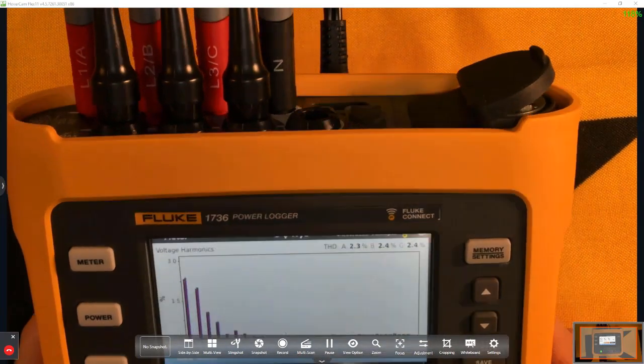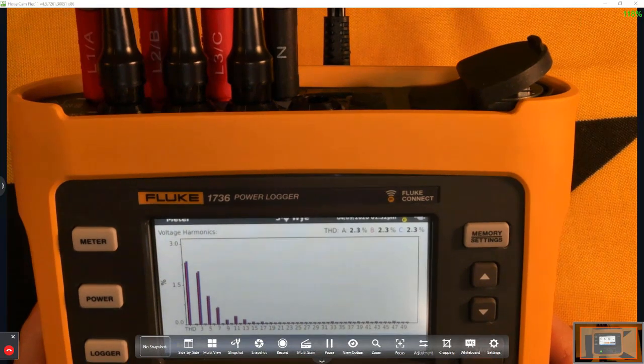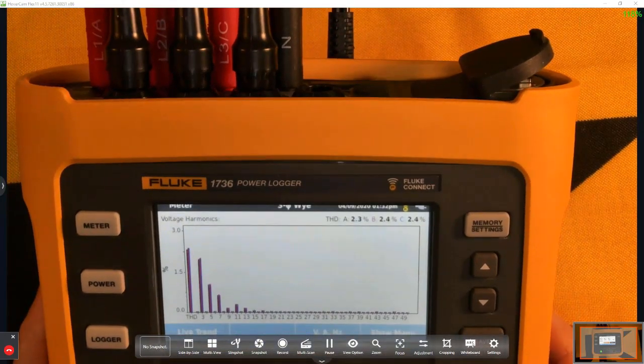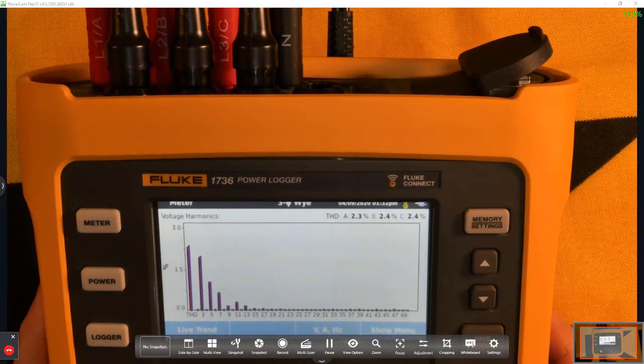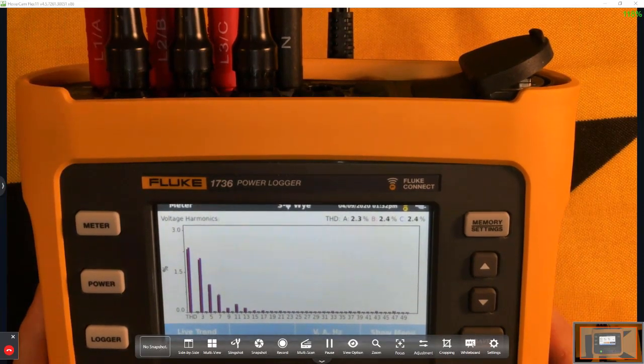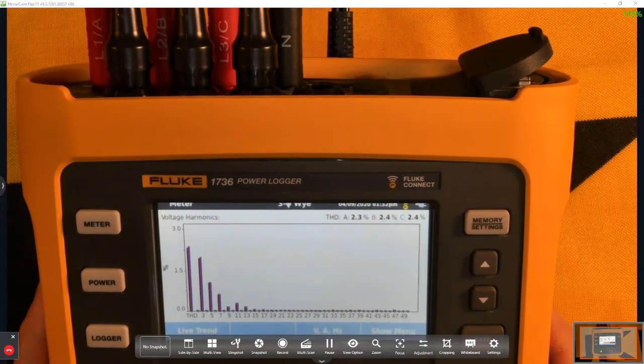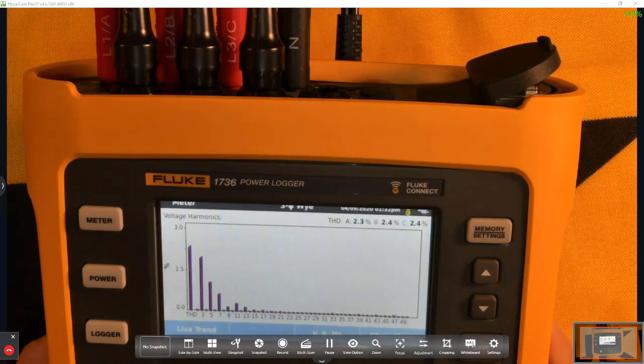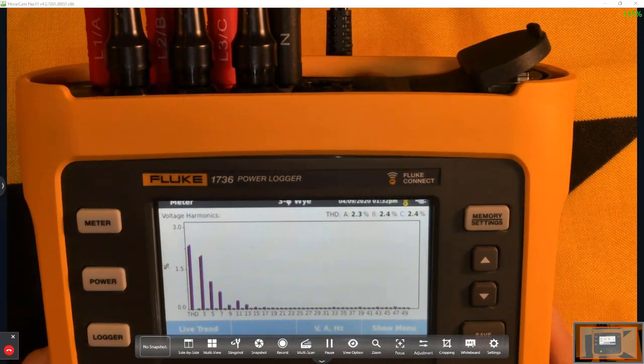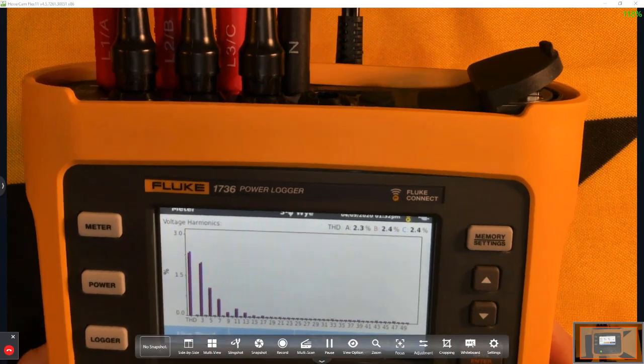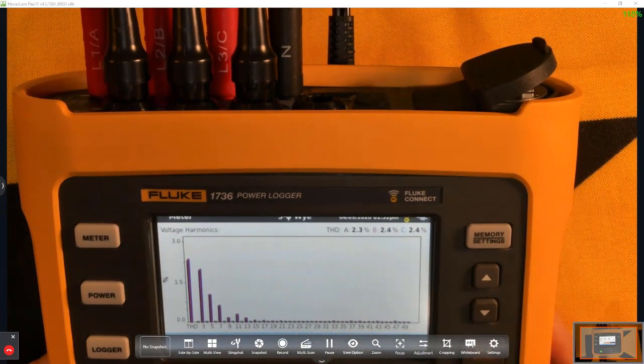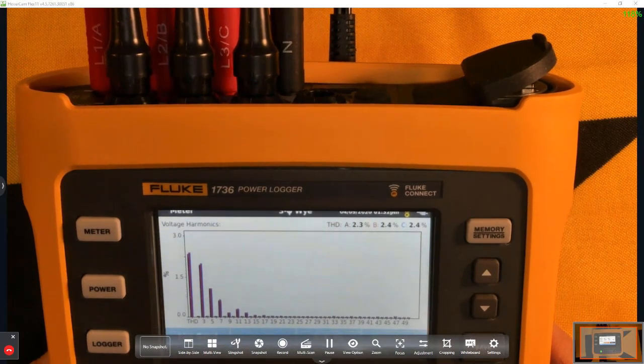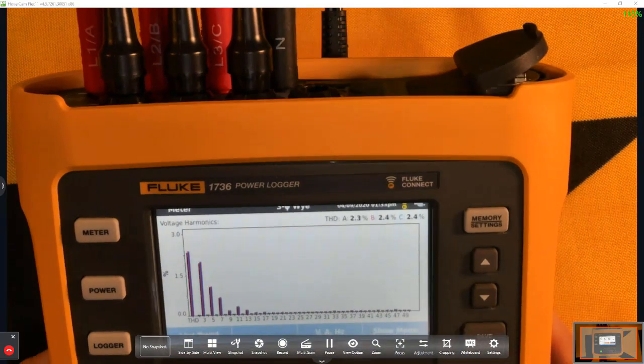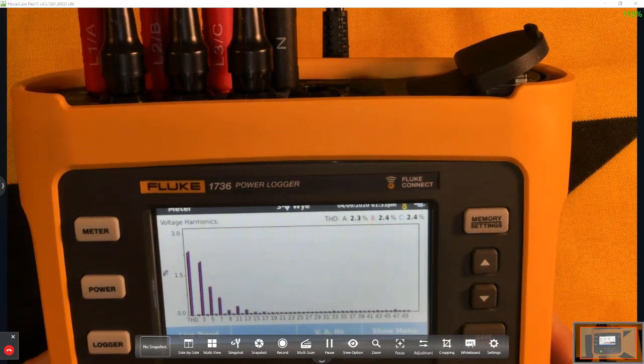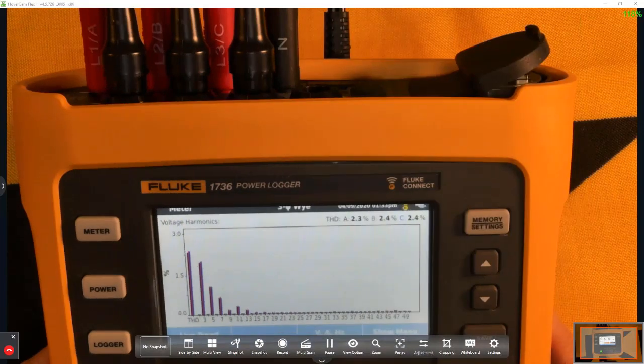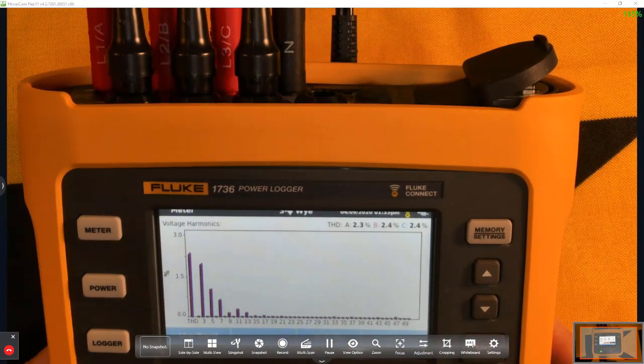The other thing we were discussing is applications involving harmonics. Usually having transformer problems, damaged power factor correction capacitors, or motor loads overheating that maybe weren't before, could be a source of harmonics. The 1736 and 38 give you the ability to measure individual harmonic orders, and if you're using the 32 and 34, you can also look at THD. So you can gauge if there really is harmonic content that would be a possible issue needing more evaluation, which the 36 and 38 can also do.